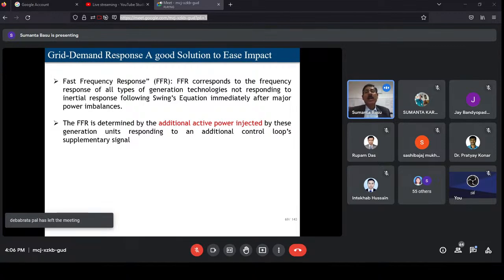As I also told earlier, there shall be fast frequency response. That is the need of the hour. While we are talking about the smart grid, fast frequency response is only possible by the renewable energies, because all rotating machines have their own system inertia, and together, for all generating stations, the total system inertia is the summation of the individual machines' inertia. And that is a slow process.